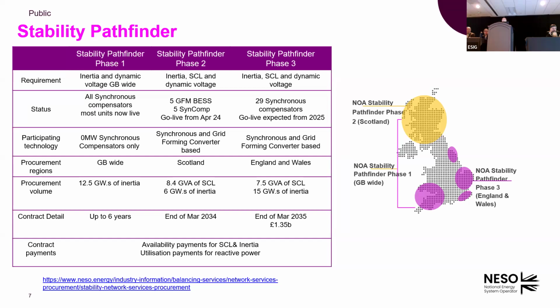We ran three stages of the Pathfinder project, looking at different areas of the GB system. We published information to the industry saying how much we want in terms of inertia support and system strength support or fault level support, and by which year, in which location. Any generator that wants to provide the service has to meet our grid forming specification requirement. They need to be grid forming first before they can participate in the market, and they can submit their price and also a technical validation report, for us to choose the best solution to meet all these requirements.